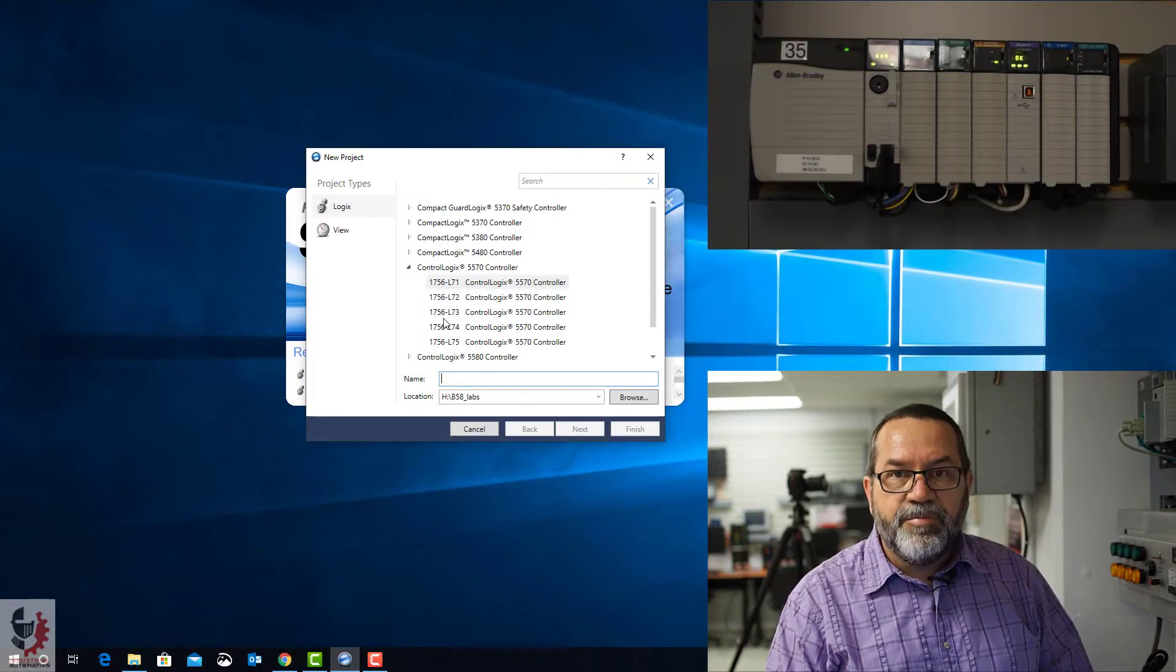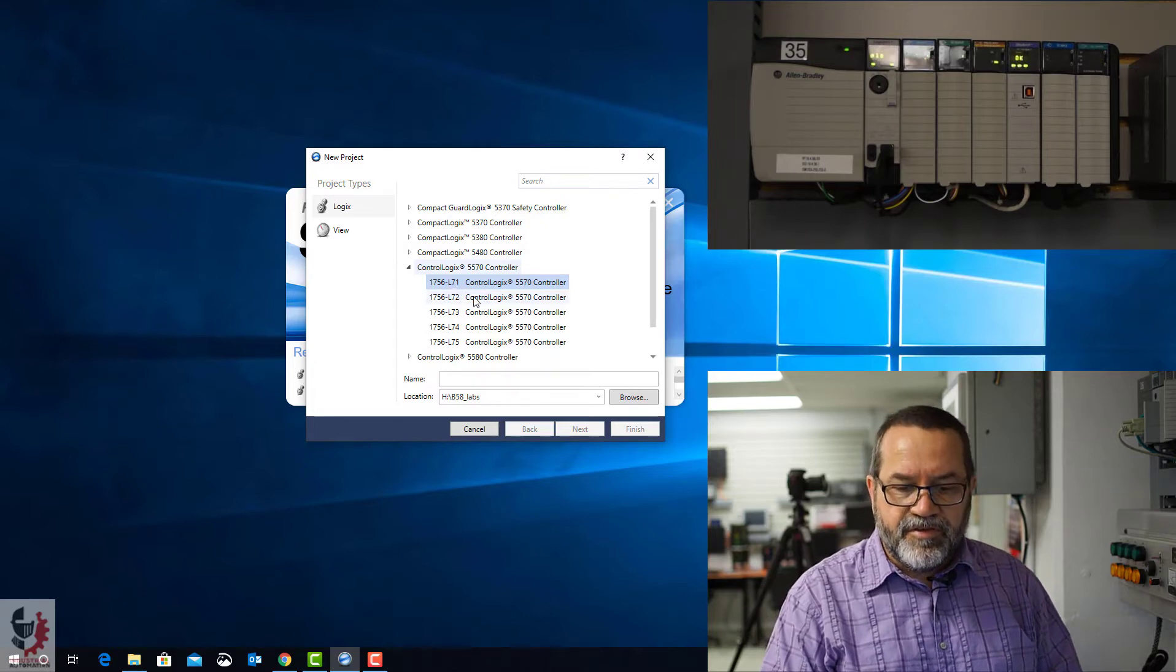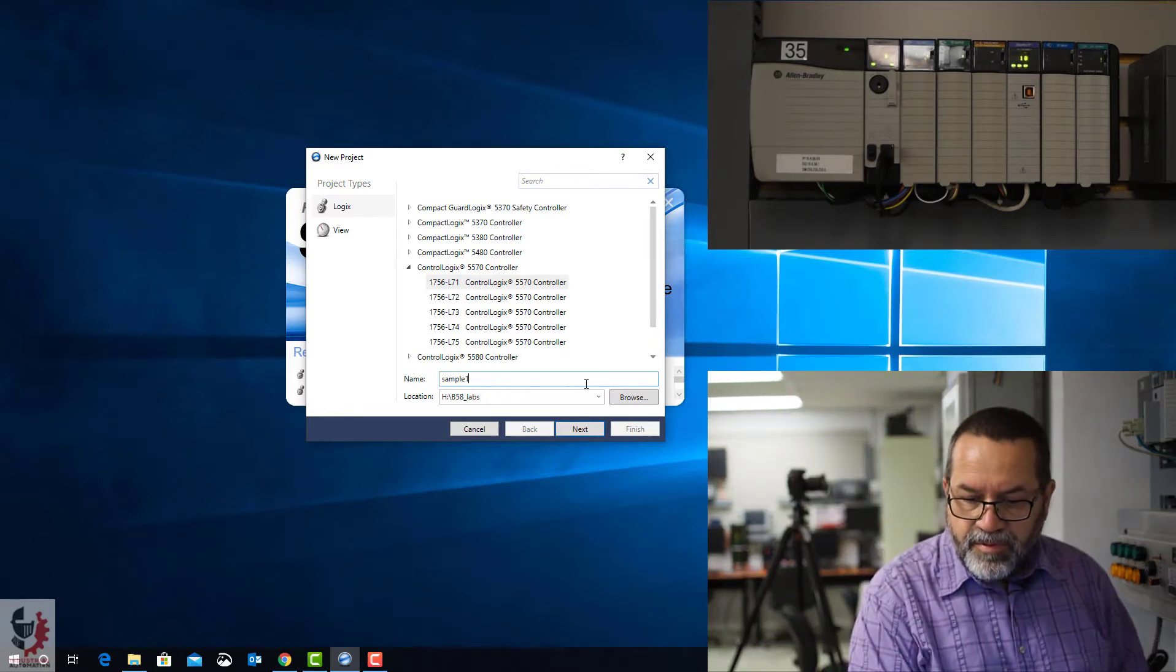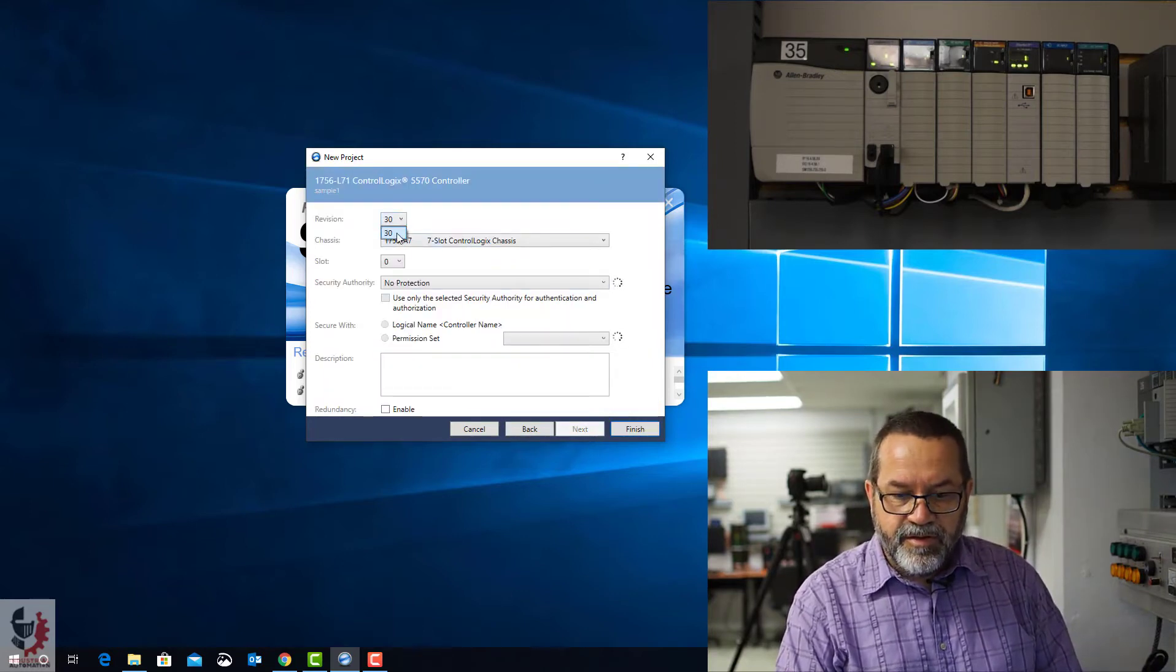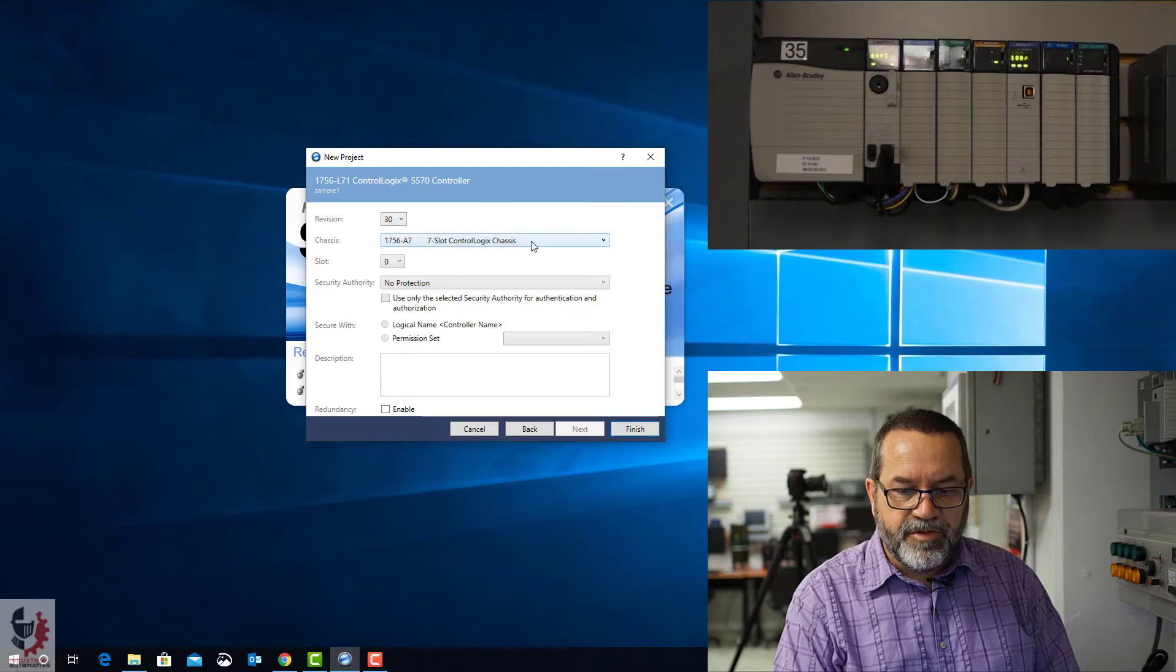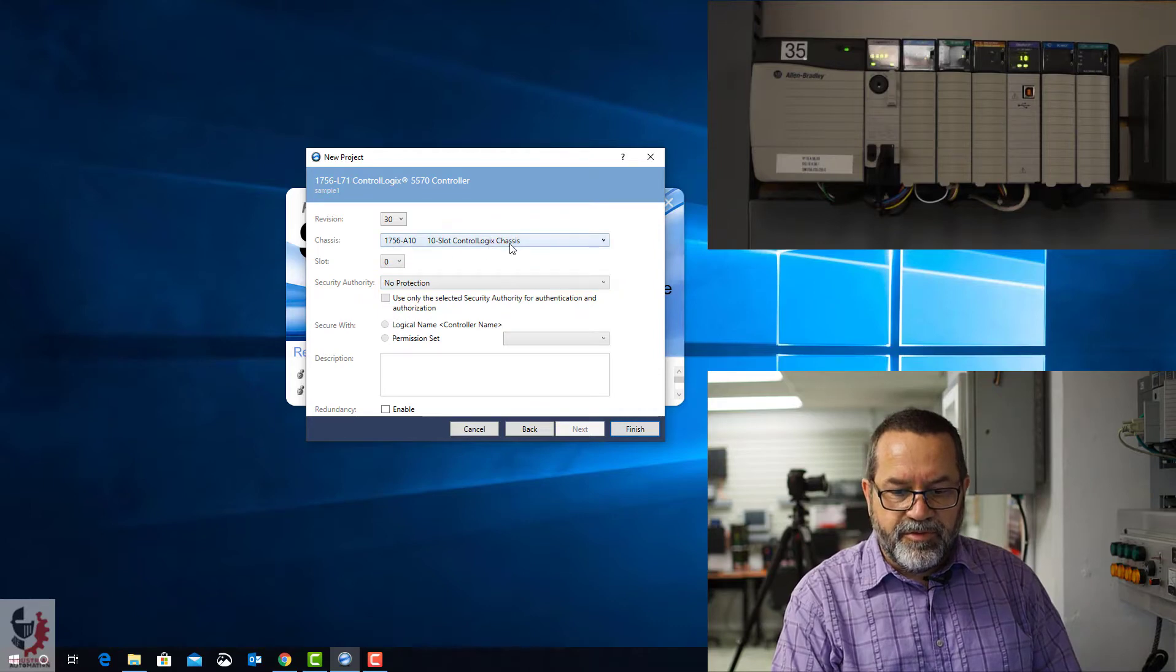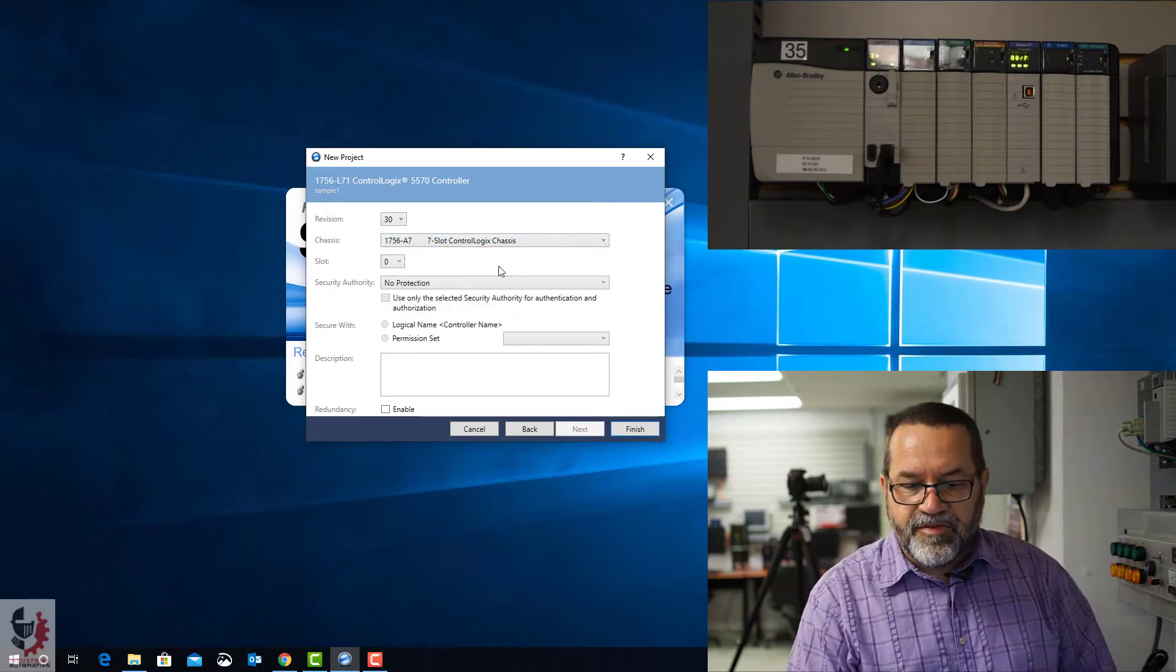I'll make a new project. And the one we're using is the 1756-L71, and that matches our controller. I'm going to call this sample 1. I'll hit next. Now here, we've only currently got revision 30 of the Studio 5000 installed, so that's what we're using. And this one's really important. Most of these computers in the lab default to 10-slot chassis. If you leave it at 10-slot chassis, it's not going to work. You need to set that to 7-slot.